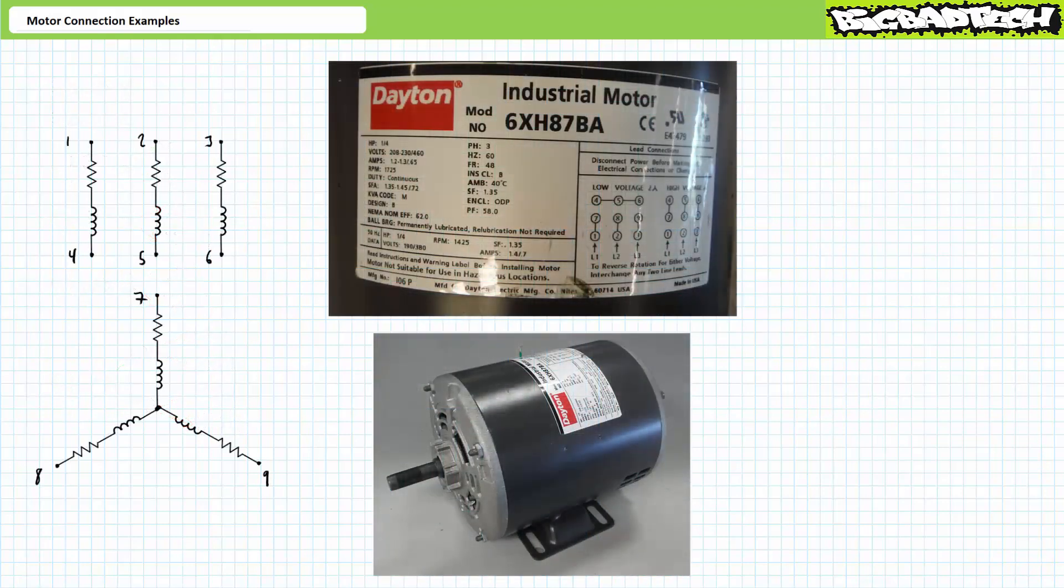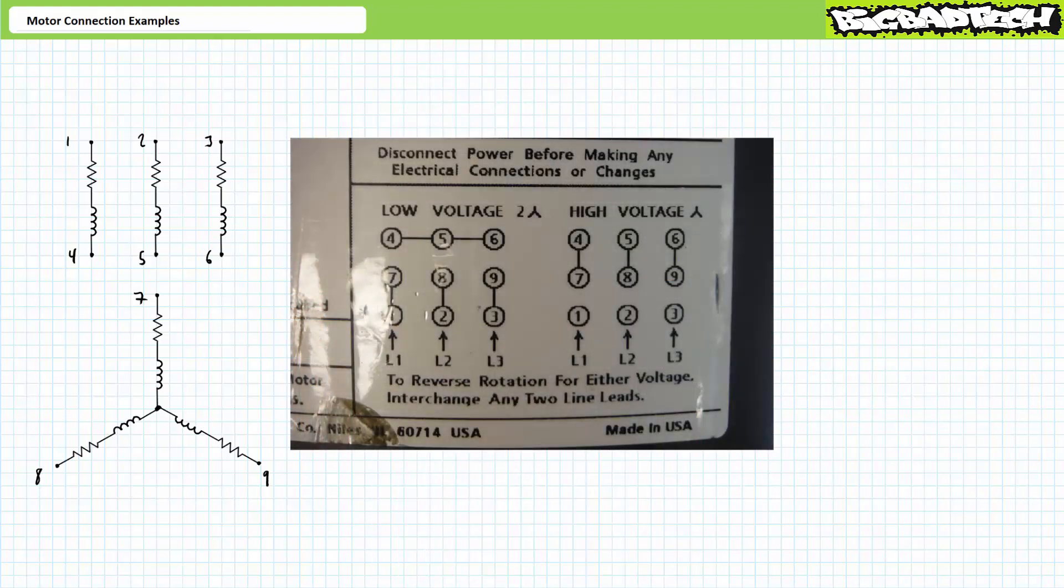First up is a quarter horsepower Dayton motor with the following motor nameplate information including a motor connection diagram on the right hand side. It looks like this is a nine-lead motor. Judging from the four-five-six connection in the low voltage configuration, this is most likely a nine-lead Y configured motor. Let's use an ohmmeter to verify this hypothesis.